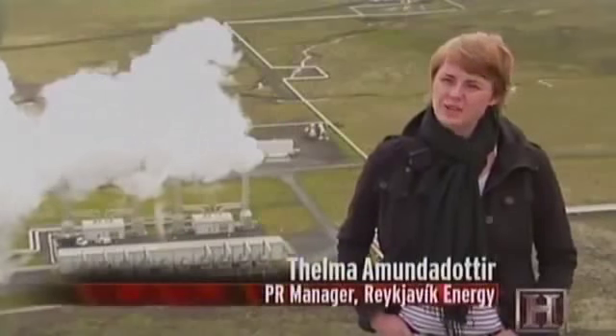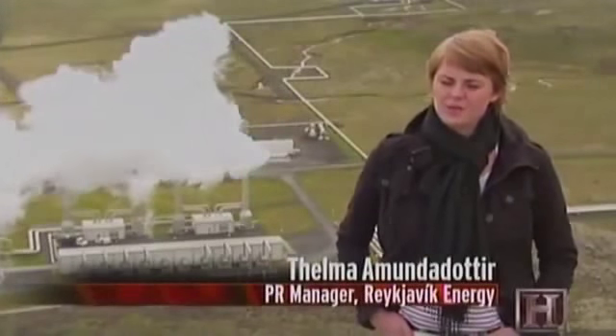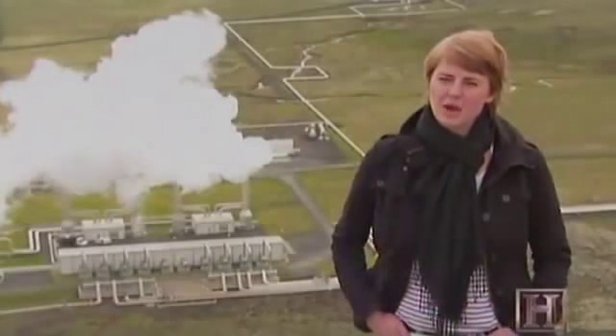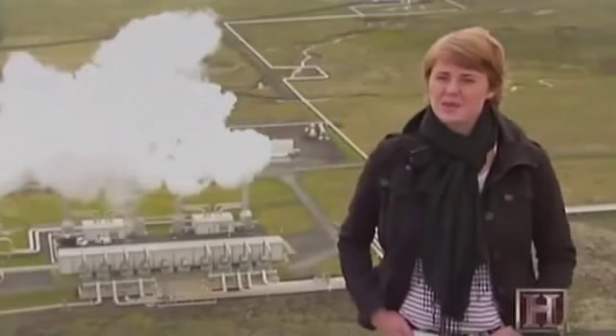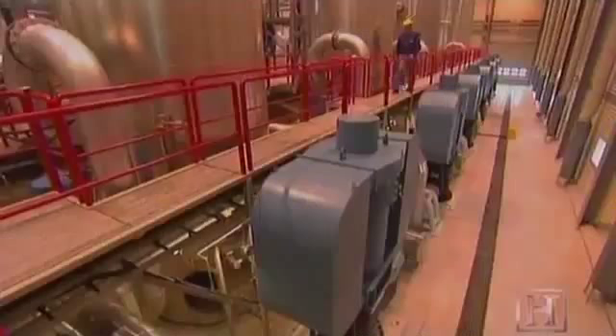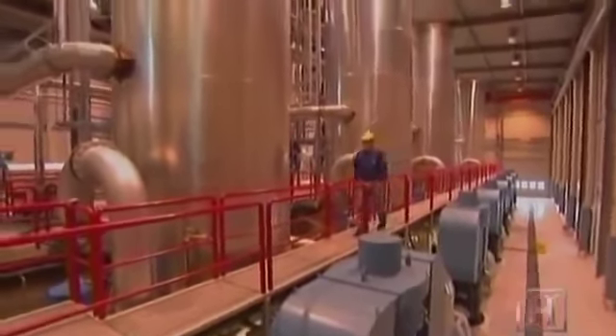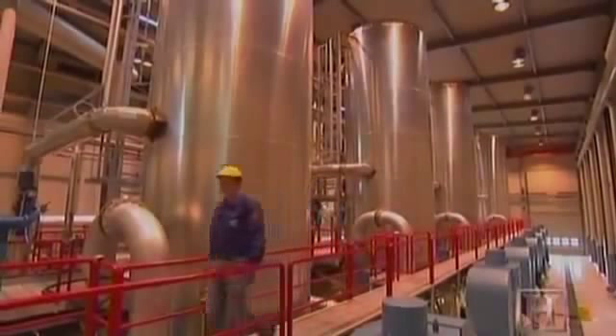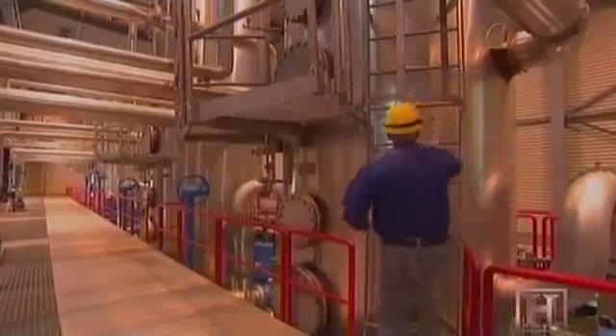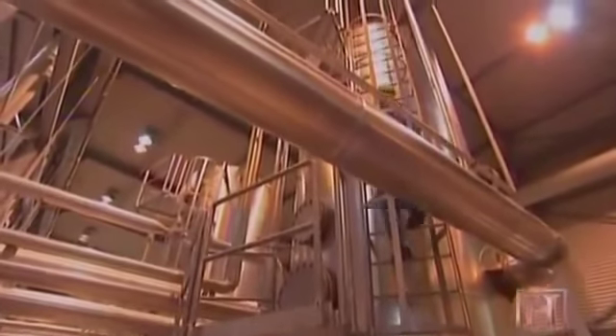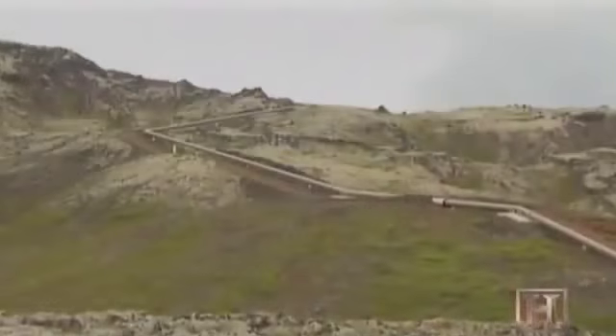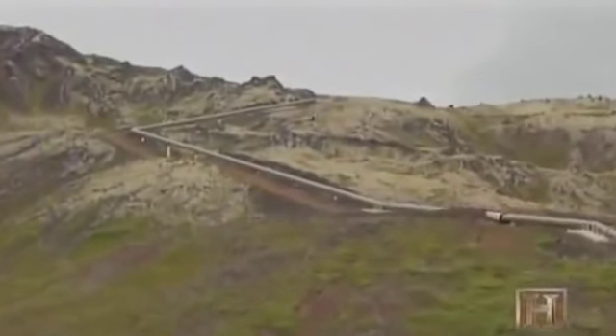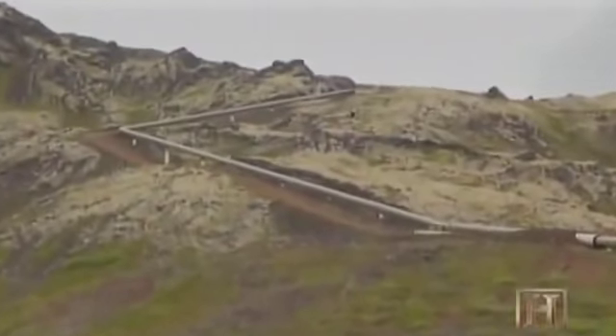125 Fahrenheit is not hot enough for us, so we have to heat the water a little bit more, up to 86 degrees centigrade. It's about 187 Fahrenheit. And we do that in a heat exchanger. Inside the heat exchanger, the geothermal brine rapidly brings the fresh water to its 187-degree target temperature. The now scalding fresh water is pumped into the pipeline as it climbs uphill. And from there, the water flows along the pipeline by gravity to Reykjavik.